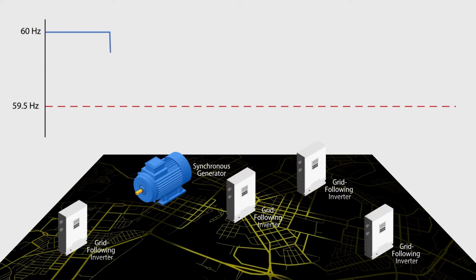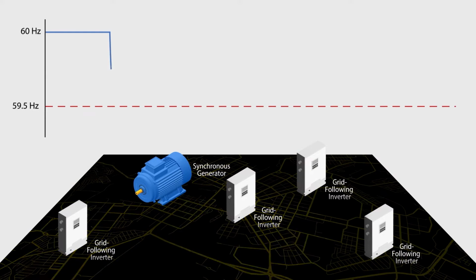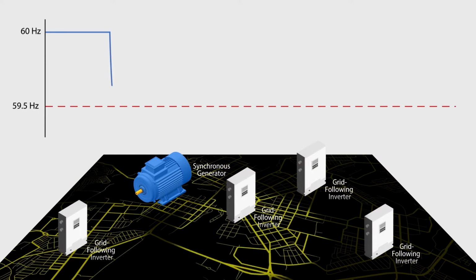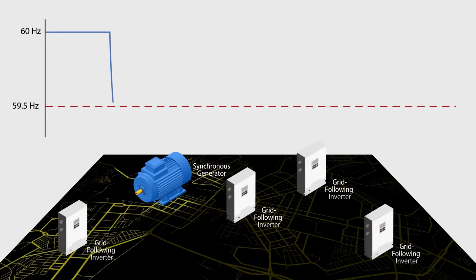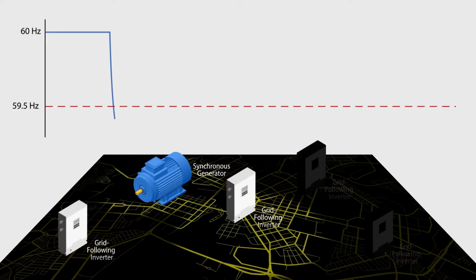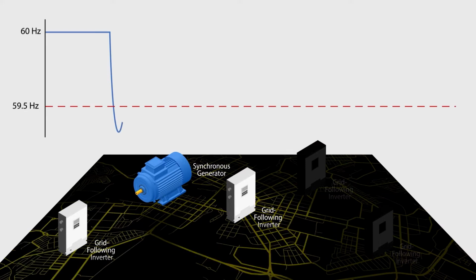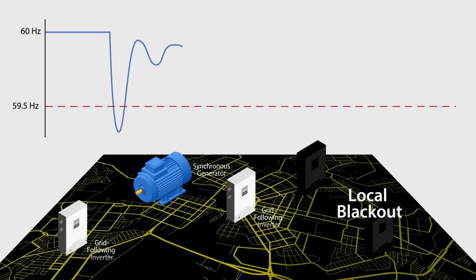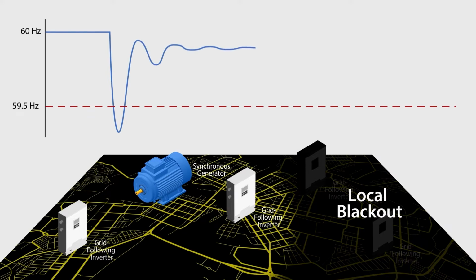This causes the frequency to drop quickly, while the remaining generators and inverters try to stabilize the grid. As the frequency drops below 59.5 Hz, the grid automatically begins an emergency recovery scheme that temporarily cuts supply to some areas, causing local blackouts. At last, the resources restabilize the frequency, and minutes later, the power is restored. Meanwhile, grid-following inverters inside the blackout cannot provide power because they have no voltage or frequency to reference.